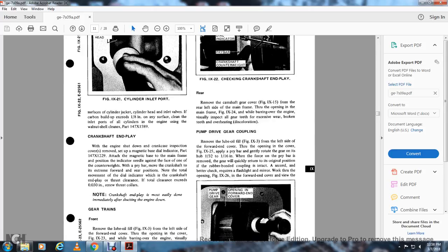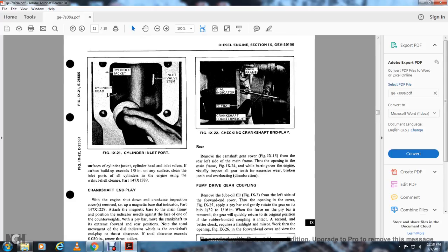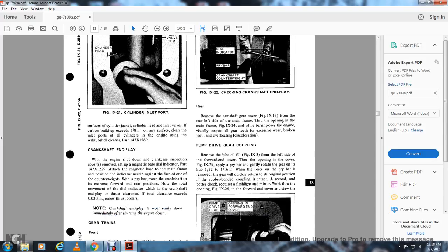While the lube oil filters are removed, check the pump drive rubber bonded coupling behind the coupling, seated to the pump driver coupling section. Figure 9-22 shows checking the crankshaft end play with the mainframe dial indicator, pry bar, and crankshaft counterweight. Gear trains — rear: Remove the crankshaft gear cover (figure 9-15) from the right (left) rear side of the mainframe opening. Visually inspect all gears for excessive wear, broken teeth, and overheating/discoloration.